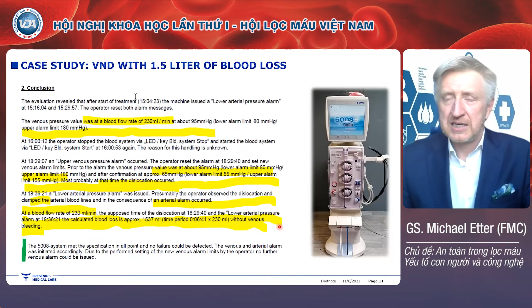When you have a lower venous pressure alarm, there are many causes for this, as you can see here, from, of course, needle dislodgement, but it can also be a clotted dialyzer, or a wet transducer protector, the piece that translates the pressure to the sensing device. If this gets wet, you cannot get accurate measures.